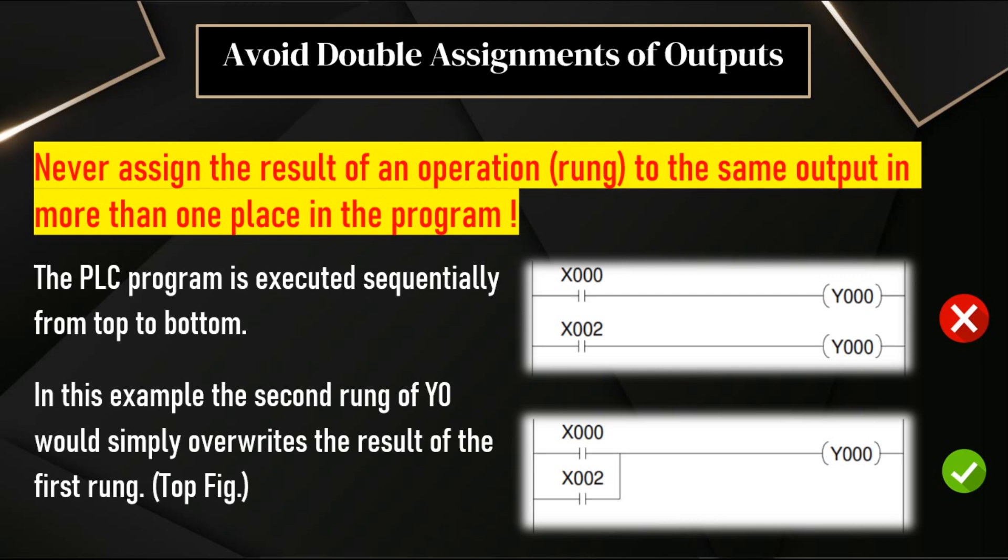This is the correct way. The both inputs X0 and X2 are in branch, are in parallel, and the output is connected. The output is used only one time. In this case, the problem will not happen. The output Y0 will be updated accordingly as per the input status X0 and X2. This is a very important topic.